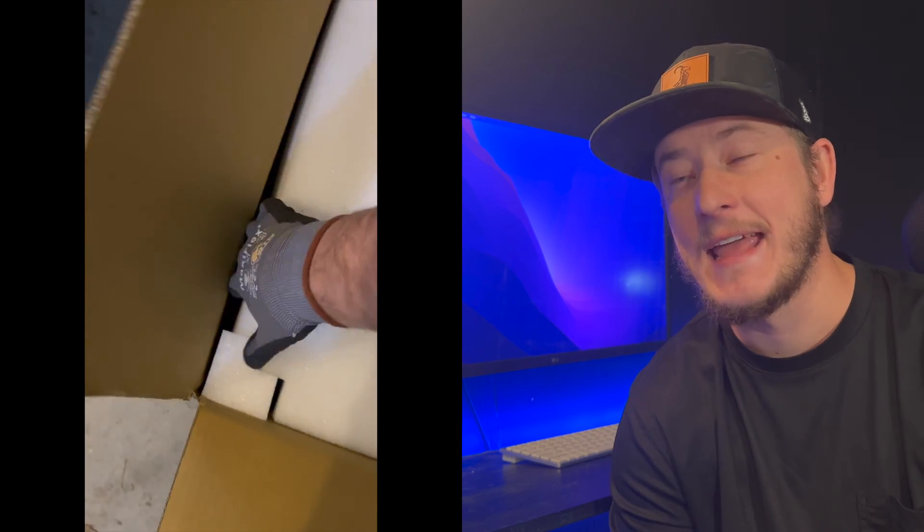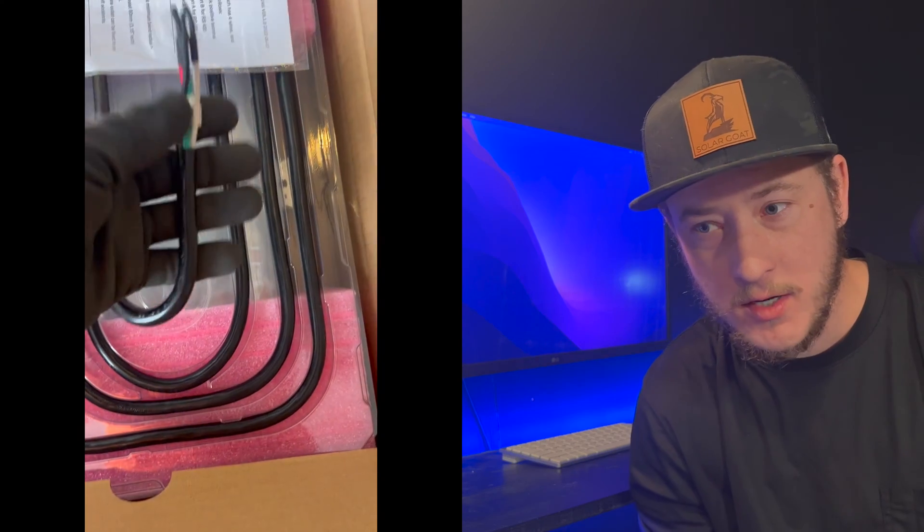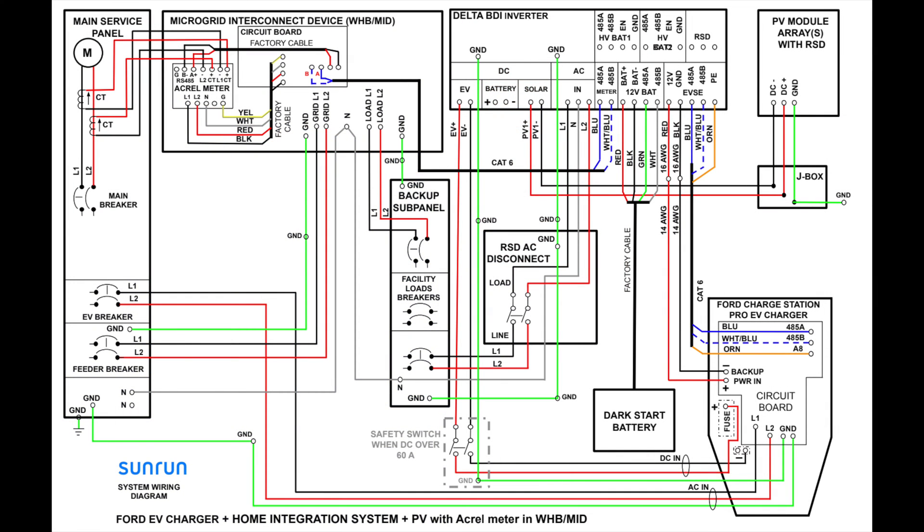The components in this system for a full backup setup are going to be, of course, the Ford charger, what's called a microgrid interconnect device, a bi-directional inverter, and a dark start battery. Optional with that setup is an LG battery or batteries, and then of course solar panels. Ford and Sunrun managed to put together the world's most confusing electrical plans, which is not helpful because this is a really hard system to wrap your mind around as far as what connects where and how it is custom made to your home. I want to walk you through how this goes together.